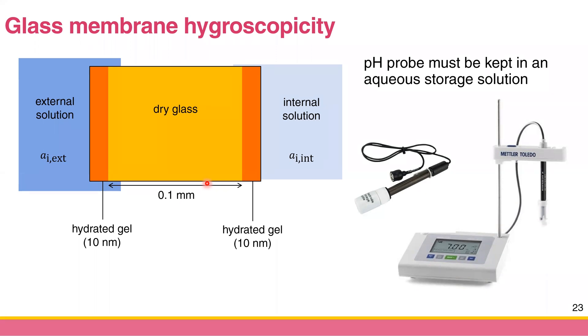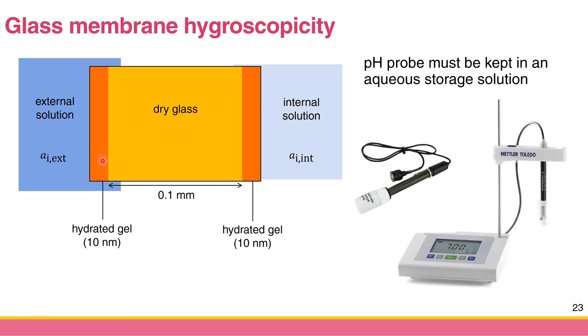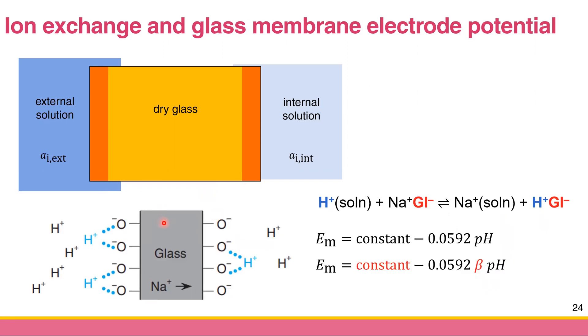In the hydrated gel, ion exchange occurs. Your glass contains sodium oxide and therefore has sodium ions. You can think of the glass as having a binding site. The ion exchange equilibrium works like this: a proton from your solution switches with a sodium ion from the glass, so at the end the glass binding site holds a proton from your sample or internal solution, and the sodium ion is released out.